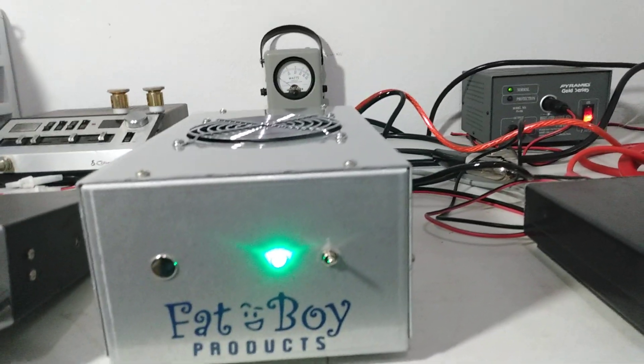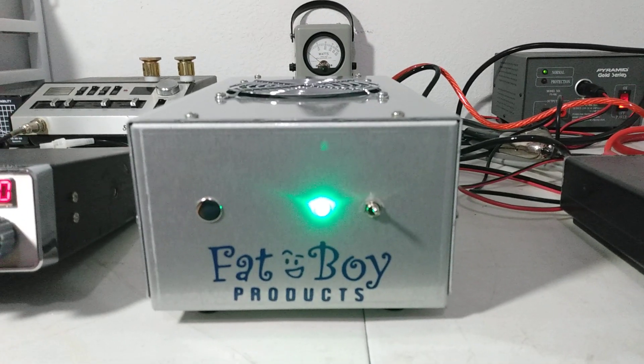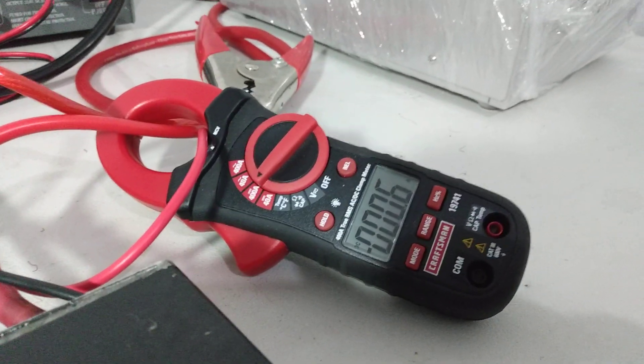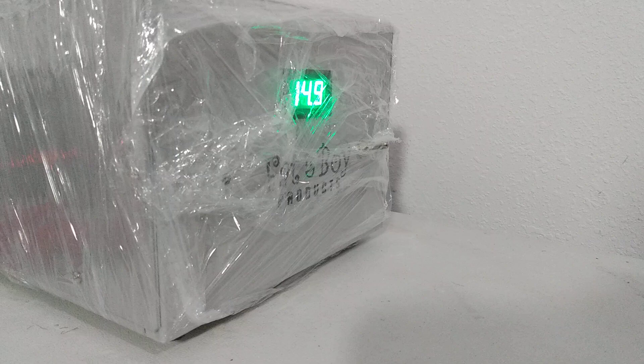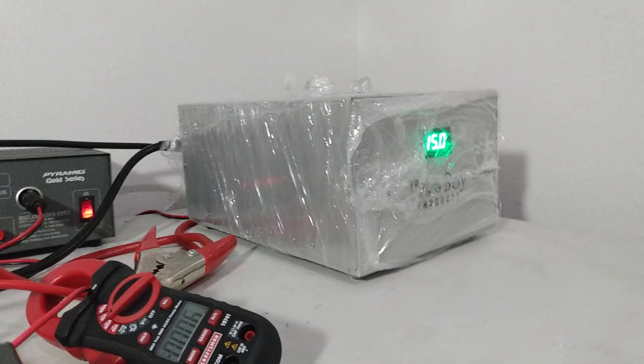Good running amp here. Been running for about 10 or 15 minutes before I did the video. And as always, I'll let them run 10 or 15 minutes after the video — make sure everything's going to hold up and we don't have any kind of crazy issues. Not drawing any current aside from basically the fan running, so that's always a good sign. As far as what it drops to — a little 14.8. Putting it on a better line than what I'm running on, it probably won't drop that much.